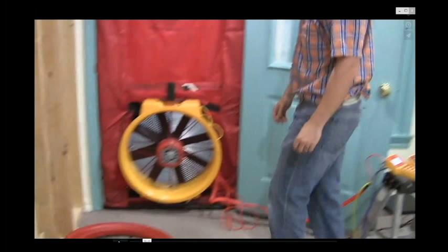So we move from a blower door test where we're thinking of the house as being a 50 Pascal absolute pressure or 50 Pascal difference between the outside, to now thinking about how a zone is in reference to the inside. So anything that is closer to 0, because the house is now inside, that's your reference, and reference is always 0, right? Right, Bill? Correct.